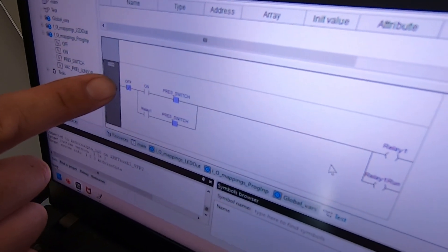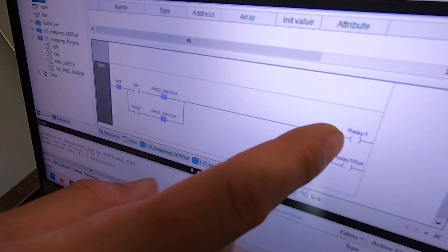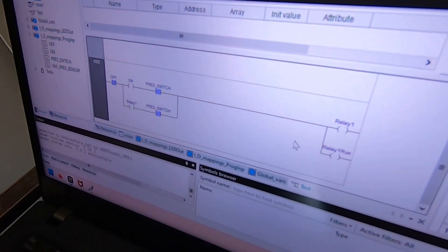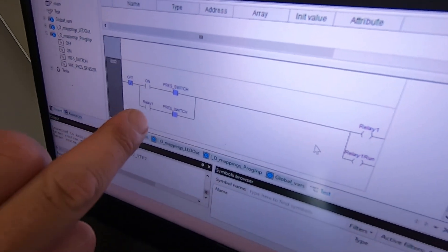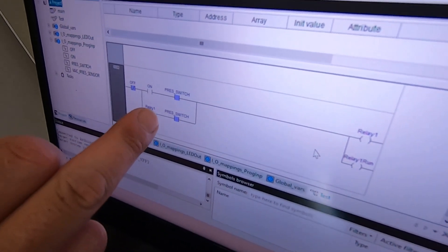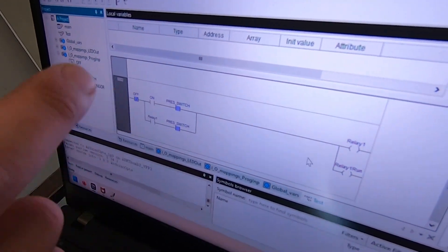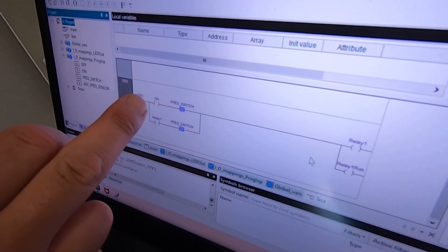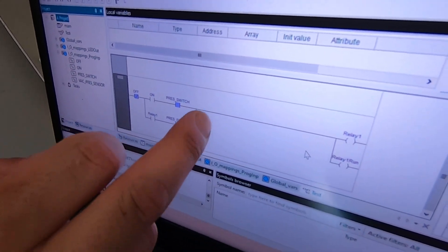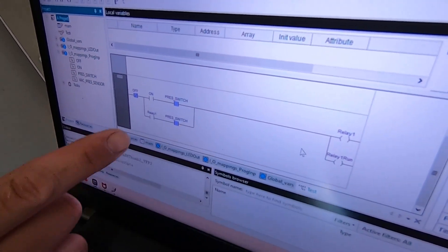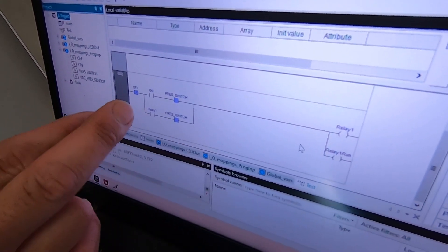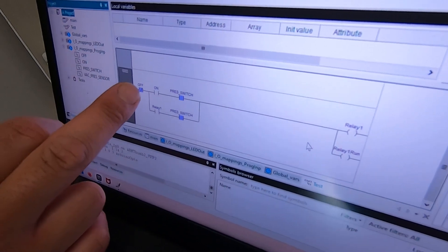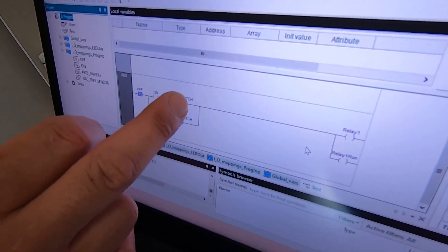So basically what happens is electricity flows through here activates the relay and then this relay gets closed and now that you let go of the on switch it'll keep passing electricity through right here. And the only thing that will stop it from passing electricity would be either the off switch or the pressure switch.